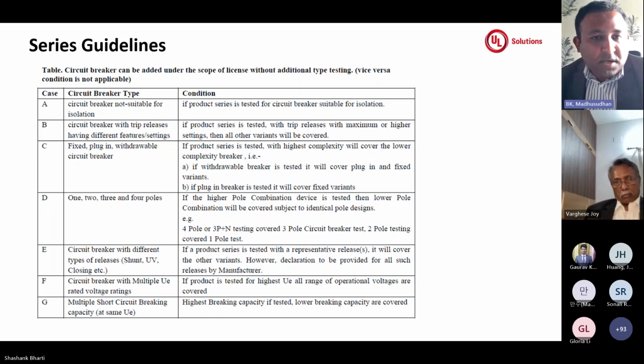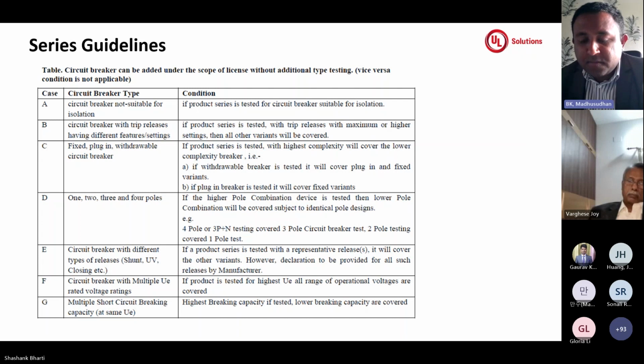So for example, if a breaker is not suitable for isolation, and later the customer wants to add this range to their complete portfolio, which is already tested with suitability for isolation, in this case there is no testing involved, provided all the constructions and other requirements are met with the previous construction. And with the documentation updation, the license can be added. So in a similar way, there are different variants here. Again, there will be multiple trip units on breakers, where once we do reference testing on one of the highest coverage settings, then the lower coverage settings of these multiple settings can be added without any testing.